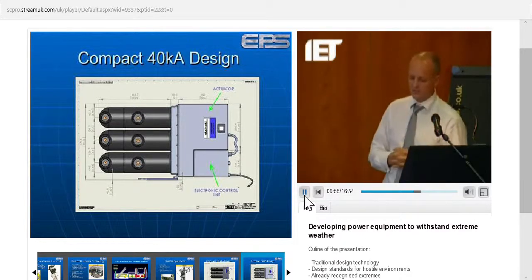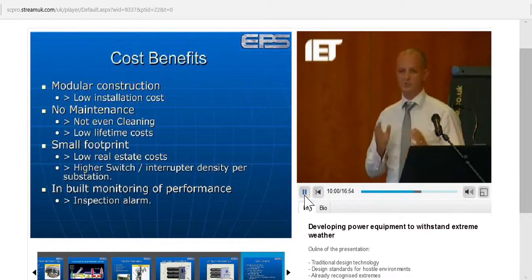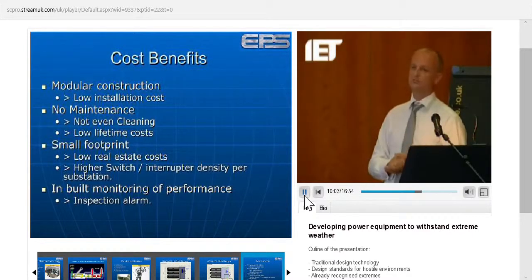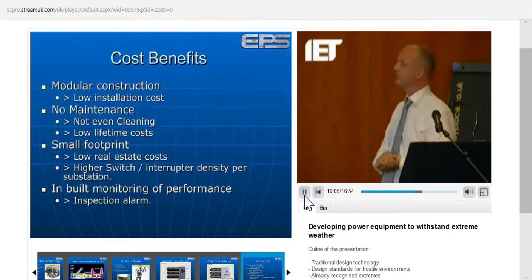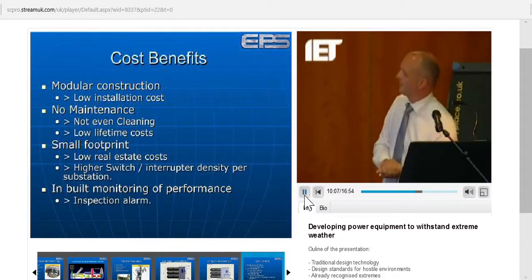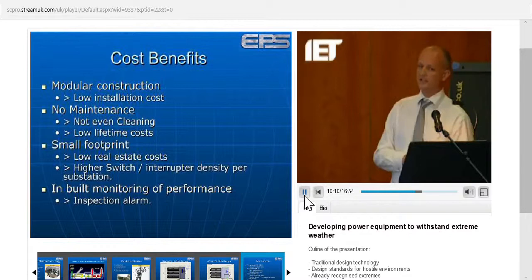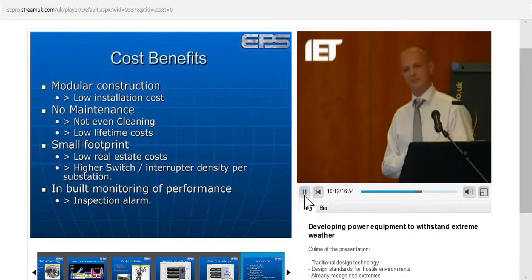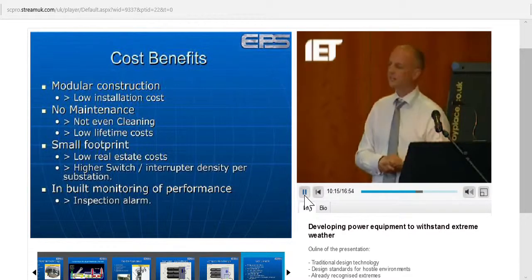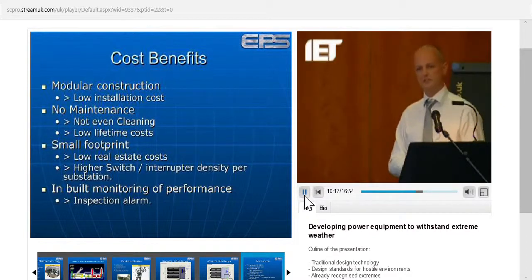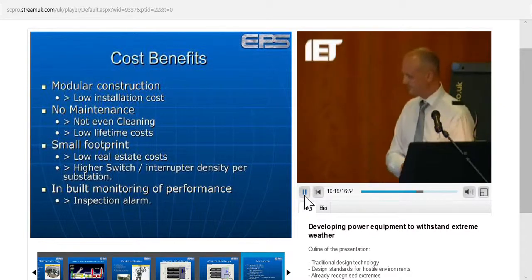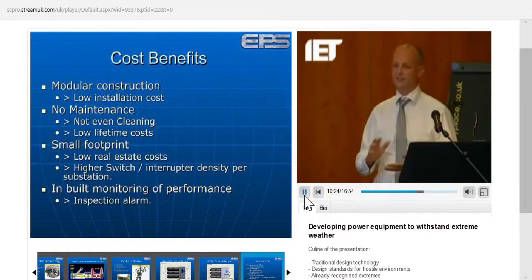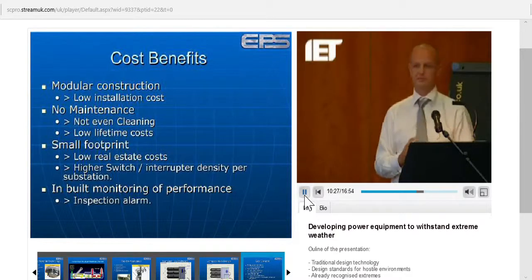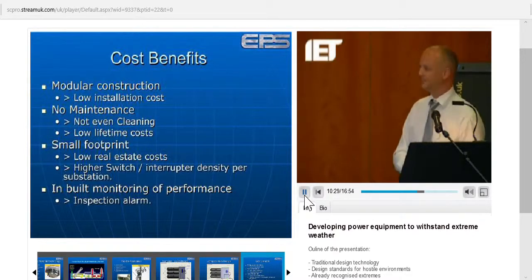So this new type of switch is designed to have certain cost benefits. It's got a low-cost insulation system which is highly tooled up. It's suitable for being manufactured in high-cost labour areas. It doesn't need cleaning. It conducts on the outside, so we don't have the problem of insulators requiring regular maintenance and cleaning and dedusting, and therefore it has a low lifetime cost. You can't maintain anything on this device. You can't maintain the vacuum interrupter because you lose the vacuum as soon as you try to.